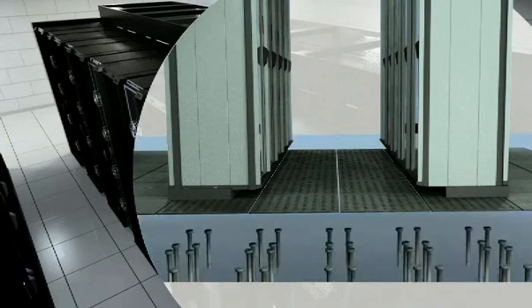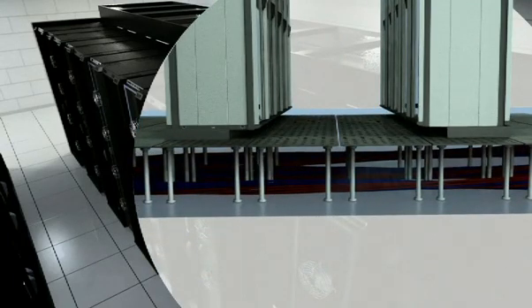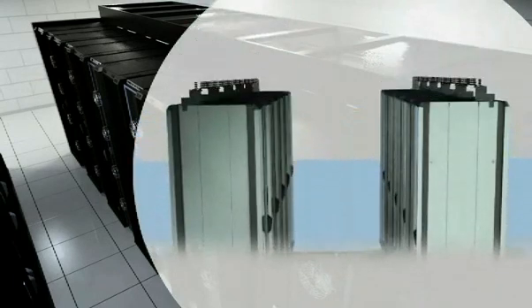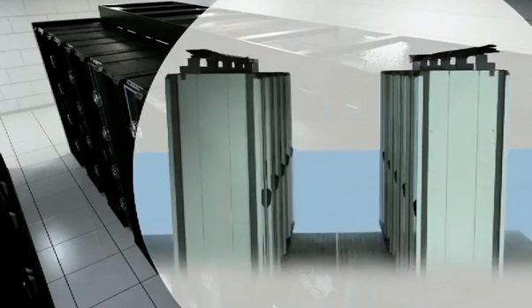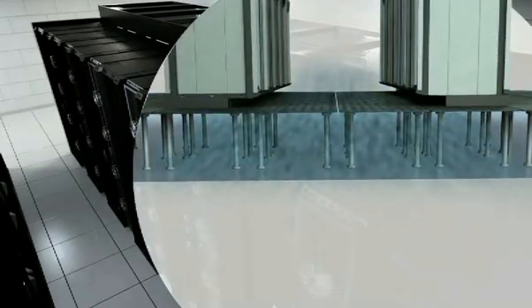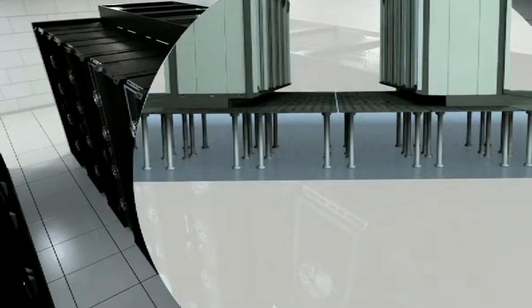Underfloor cabling systems are convenient for large amounts of cable. However, the cable mass can restrict airflow. With the Canon Raceway, the cabling is mounted at cabinet roof level, removing any air obstacles below the floor.